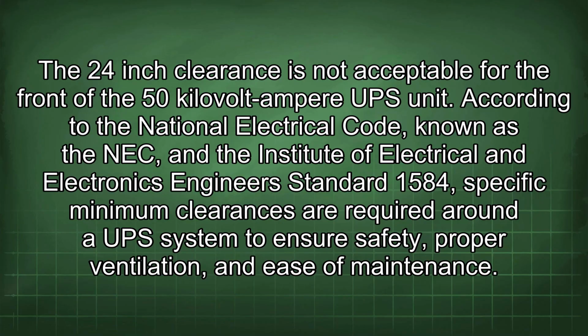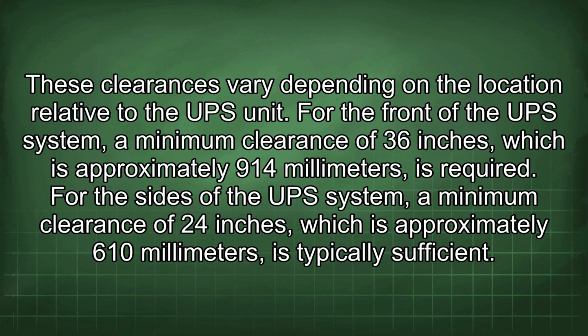24-inch clearance is not acceptable for the front of the 50 kilovolt-ampere UPS unit. According to the National Electrical Code, known as the NEC, and the Institute of Electrical and Electronics Engineers Standard 1584, specific minimum clearances are required around the UPS system to ensure safety, proper ventilation, and ease of maintenance. These clearances vary depending on the location relative to the UPS unit.